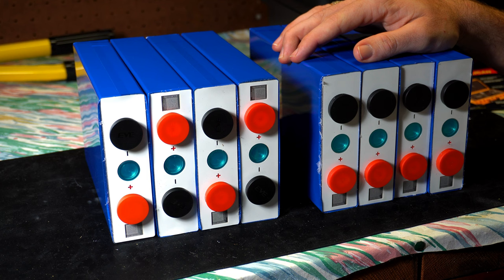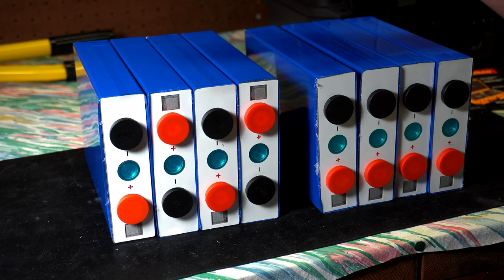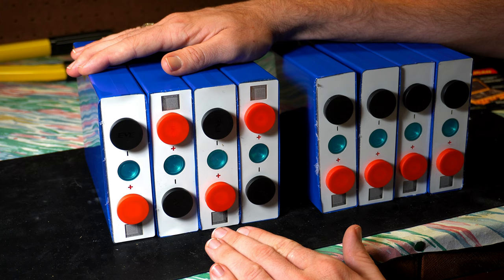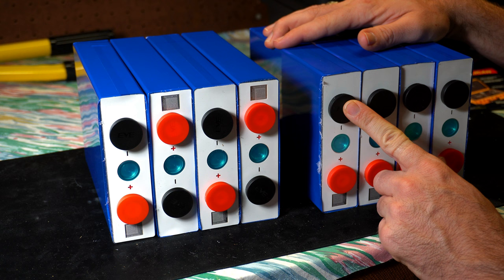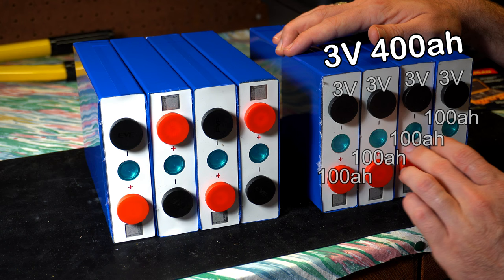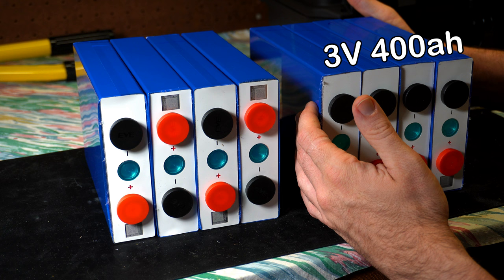I'm going to give you a very brief demonstration of parallel versus series connections of a battery cell. In parallel, the voltage stays the same but the amperage increases. In series, the amperage stays the same but the voltage increases. For simplified math, we're going to say that each cell gives you 3 volts, 100 amp hours. So in this situation, you have a 3 volt battery, but the amperage increases: 100, 200, 300, 400 amp hours. So you have here a 3 volt, 400 amp hour battery.